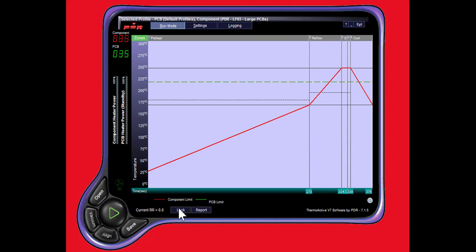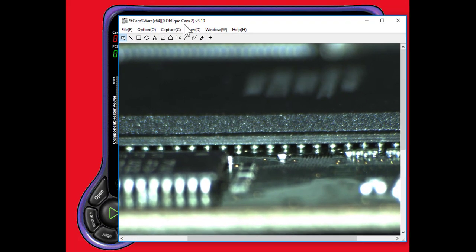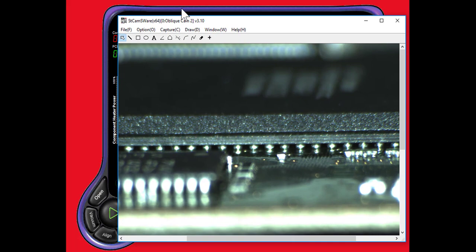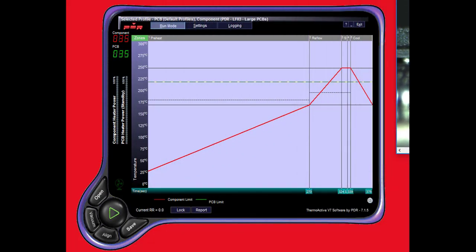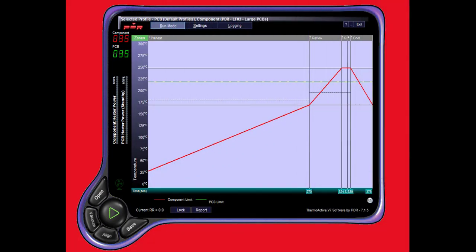Also password protected for management will allow the operator to get on with daily tasks and run, stop profiles. You just won't allow them to change the key variables for any profiles such as time and temperature. PDR software also provides report features for engineers reporting to CSV format or PDF format. Here in combination with PDR's software package, number of different controls: draw, capture, annotate. These pictures can be saved after drawing or annotating on them and can be included both in the process setup instruction files as well as for issuing reports for roll-up to management and customers.